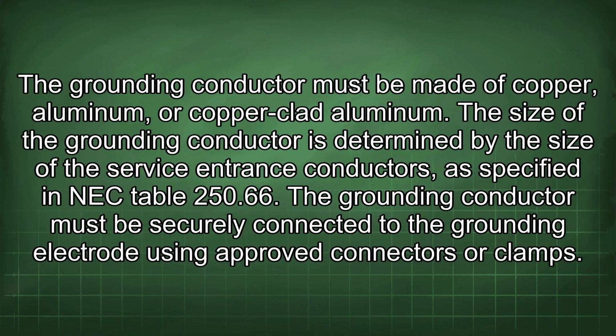The grounding conductor must be made of copper, aluminum, or copper-clad aluminum. The size of the grounding conductor is determined by the size of the service entrance conductors, as specified in NEC Table 250.66. The grounding conductor must be securely connected to the grounding electrode using approved connectors or clamps.